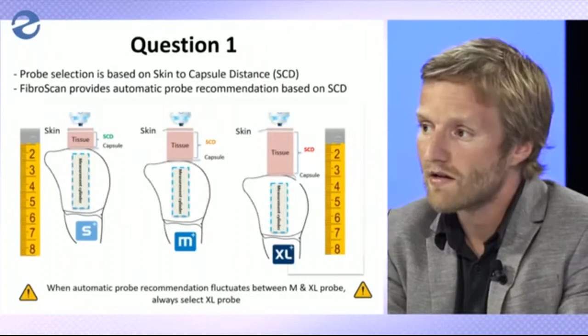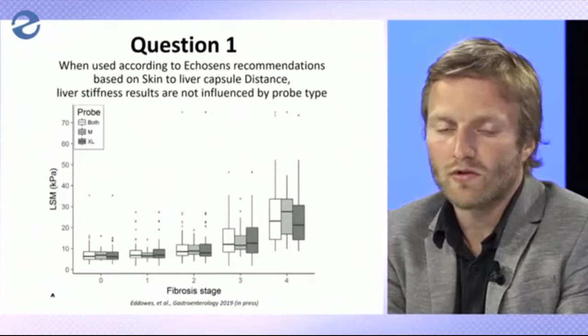Of course, in some cases you will have some doubts between M and XL, because maybe the patient is just borderline in terms of SCD. In that case, if you have any doubt, you should prefer the XL probe, because you get rid of the risk of overestimation. However, if you look at the recent data, and this is, I think, the next slide, when you take into account the influence of the probe on the liver stiffness values, and these are data published this year, we can see, this is a UK study, that no matter the stage of fibrosis, if you use the correct probe based on the official recommendation from Echosens, there is no difference in the stiffness value. So we believe at Echosens that we could use the same scale of values for M and for XL probe, if, of course, the probe is used based on the skin to capsule distance.